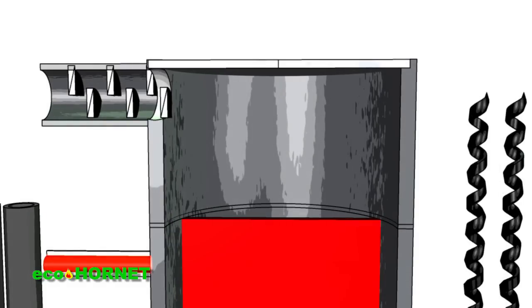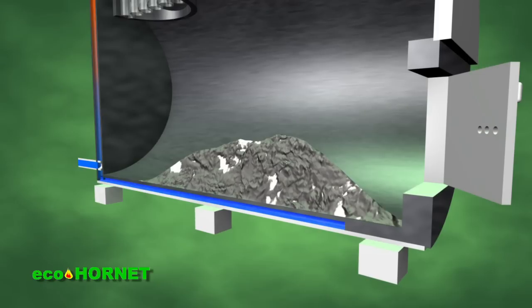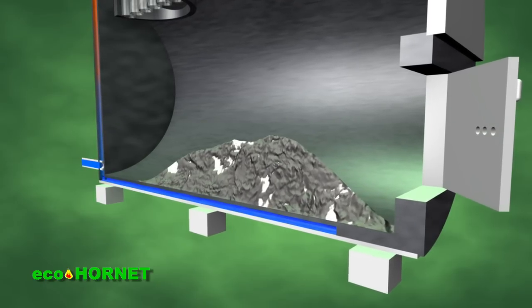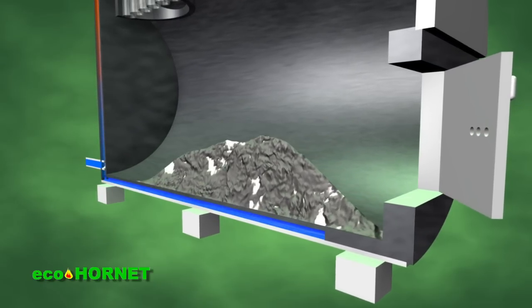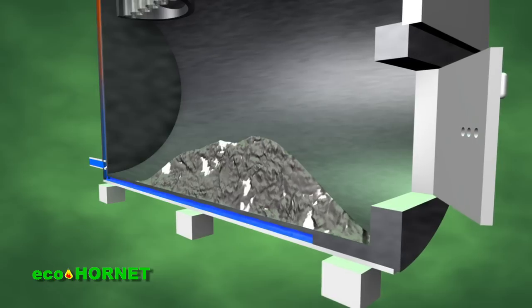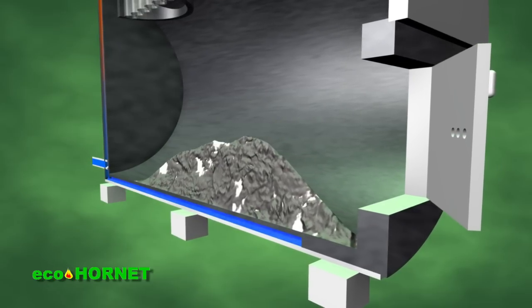Another area was designed above the pipes of the convection area of the heat exchanger, which provides both the uniform absorption of the gases through the pipes, as well as a reduction of their speed, which allows the ash microparticles involved to deposit, stop, and then gravitationally return through the pipes in the ash bin. The horizontal cylinder also functions as an ash bin. In the area below the burner, there is a door designed for the disposal of ash. The ash is disposed of every 30 days of operation for the heating system.